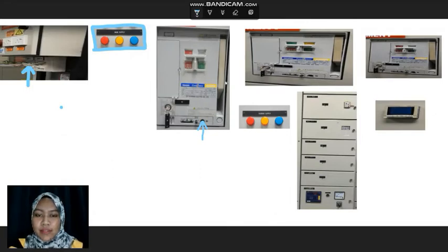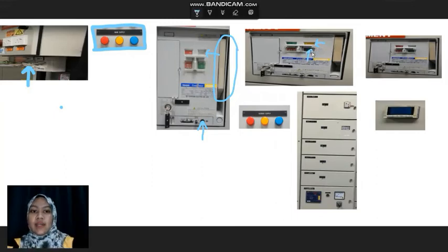Then we must turn on the air circuit breaker. In order to turn it on, the coil must be in charge position, but here we can see that it is in discharge. So in order to charge the coil, we use this charging handle and pull it up and down a few times until the status changes to charge position. After the coil is charged, we push this green button and the air circuit breaker will turn on. After that, we check the bus bar supply here.